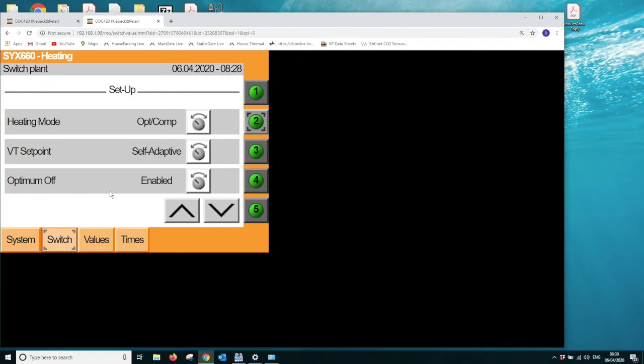Okay, optimum off. Throughout the day, the controller will be monitoring the current room temperature, and it calculates the warming downtime or the cooling downtime of the building. So if you were to turn the heating off in the building, how quickly would that heat in the room decline over time? And so the controller monitors that, and it can make a prediction of when to turn the heating off prior to the programmed end of occupancy. So if there is a little bit of surplus heat, we can utilize that heat in order to save some energy by running the plant to the end of occupancy time.